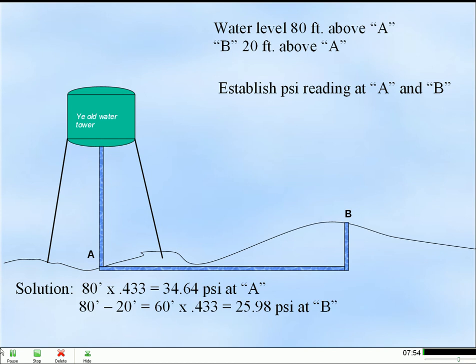Just as height increases the static pressure of a system, the reverse is also true. A rise in elevation above the water source will decrease the pressure. For example, fire sprinkler systems in tall buildings must compensate for the reduction of pressure due to the change of elevation. Pumps and storage tanks on the higher floors are required to maintain sufficient water pressure.